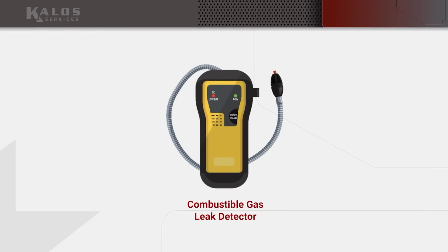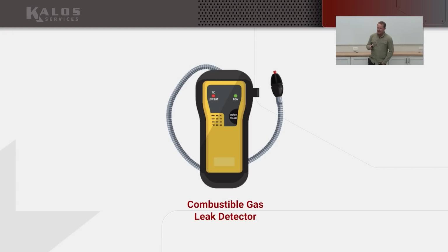Combustible gas leak detector. That is not the same thing as flue gas detection. So it has nothing to do with what's in the flue. You should not have combustible gas exiting the flue on a gas furnace or a water heater or a pool heater, right? If you actually have natural gas or propane or LP leaving the appliance, you've got much bigger problems, right? It's supposed to catch on fire before it goes out. The purpose of a combustible gas leak detector is so that you can go around and make sure that all of your connectors, everything, is not leaking gas. Because in terms of the things that we're really trying to prevent here, and we're going to cover this in another slide, having unspent gas that's just leaking around a furnace or a water heater is among the most dangerous, because that's what we call a bomb.